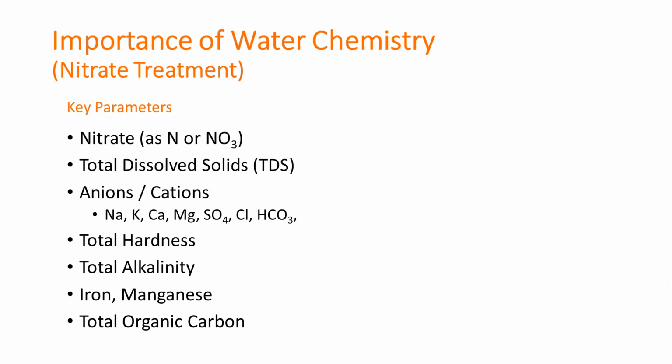Water quality, as in any treatment technology, is very important. Two of the key items that we have to have for ion exchange design would be nitrate and sulfate, because the sulfate does become a competing ion on that resin for the sites.